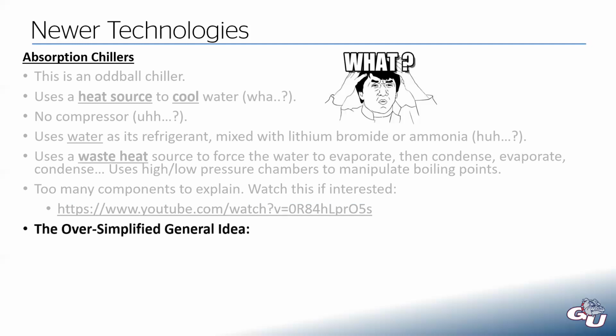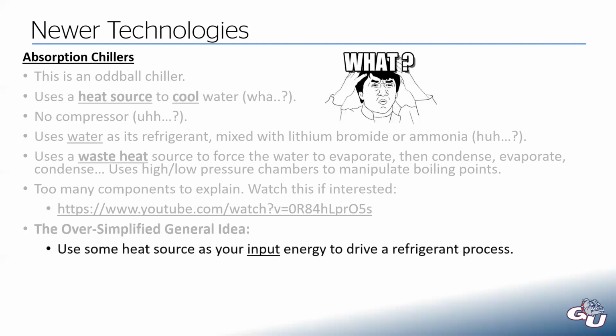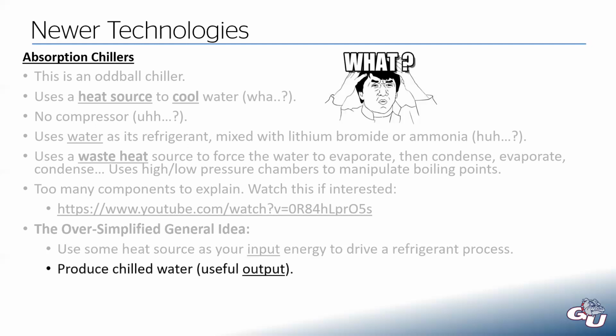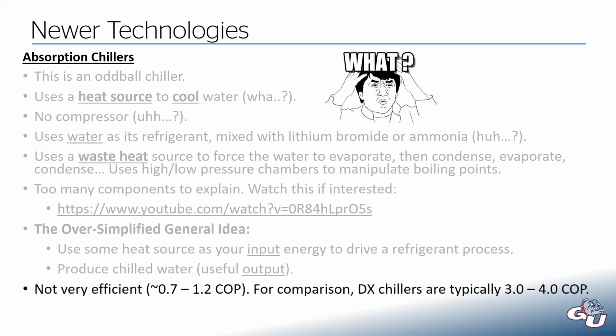But the explain-like-I'm-5 oversimplification is we're going to take some heat source, and that is our input energy to drive this strange refrigerant process. And then we're going to produce some chilled water. That's our useful output. It's not very efficient, 0.7 to 1.2 COP. That's not that great. By comparison, DX chillers are right around 3 to 4 COP.